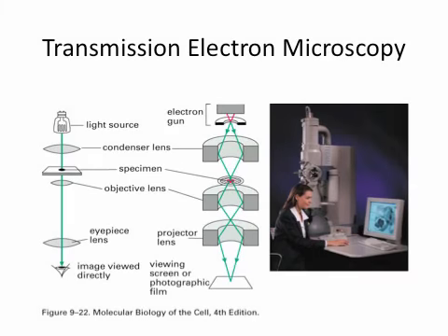Okay, so that was SEM. So let's move to TEM. And TEM is a slightly bigger machine. This picture here is one of the smaller ones, actually. We have a huge one now with subatomic resolution in physics. And the difference now is that the other one was scanning electrons, so you basically scatter off, and this one goes entirely through the sample, which basically means that your sample has to be really thin. So roughly, if your sample is thicker than 500 nanometer, forget it. It's just black, right? You won't see anything.